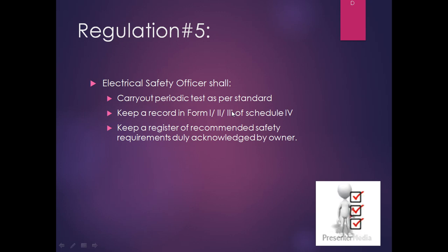Questions are asked like what kind of conductors are being used, or whether conductors of different voltages are laid through the same support or not. This kind of checklist or small objective type questions are asked. He has to fill that form, and he shall also keep a register of recommended safety requirements duly acknowledged by the owner. Now, the electrical safety officer's one of the major duties is understandably that he has to ensure the electrical safety of the plant. He should take account and note down his observations, and those observations must be acknowledged by the owner. This is also one point the CEA inspectors want to see during the time of inspection. So it is very important to keep the register of recommended safety practices, and that shall be acknowledged by the owner.